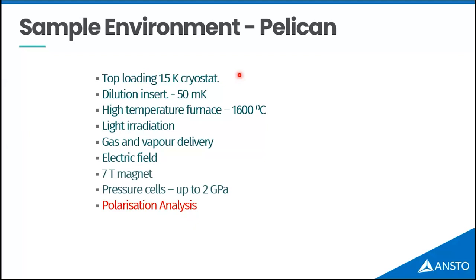We have recently commissioned pressure cells up to 2 gigapascal. Depending on the sample, we can do some high pressure experiments. We have already applied it, and 2 publications have resulted from this pressure cell. And the polarization analysis option is still ongoing, but we will get it working very soon.